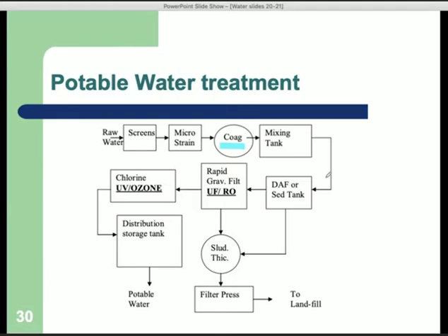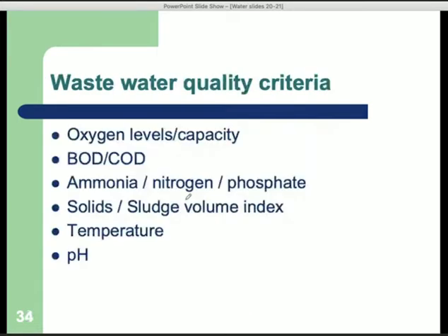So you can then do some other trickery, so you can use advanced treatment like ozone or ultrafiltration and all sorts of stuff, but that's essentially the design of a water treatment plant for drinking water. You take the very coarse stuff out, you add a coagulant, the coagulant binds all these small particles, and then the floc that is part coagulant, part particles gets retained in a sand filter and chucked away. So that's the end of me ever saying drinking water again.